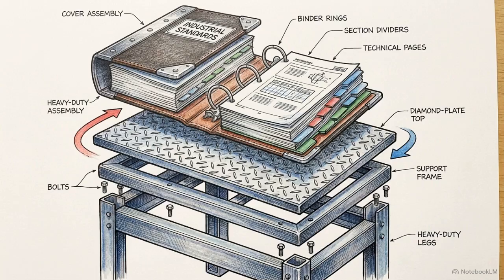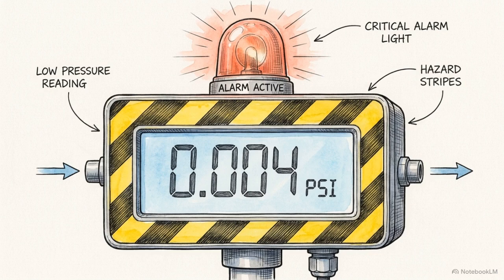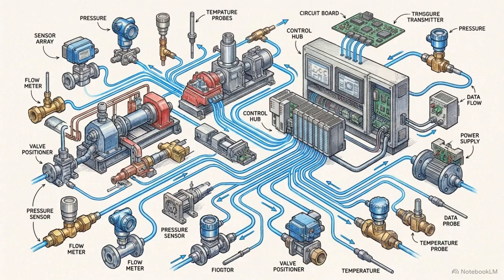This self-monitoring logic is formally standardized across the industry under the NAMUR NE43 specification. It dictates that any signal dropping below 3.6 milliamps is officially classified as a low fault condition, which automatically triggers safety interlocks and alarms. Offsetting the baseline to 4 milliamps transforms a blind stream into a continuous, self-monitoring diagnostic network.